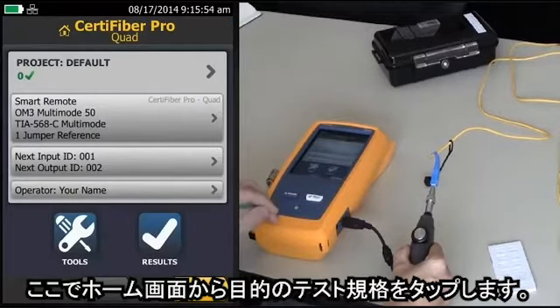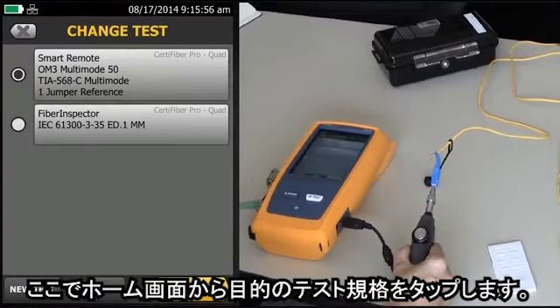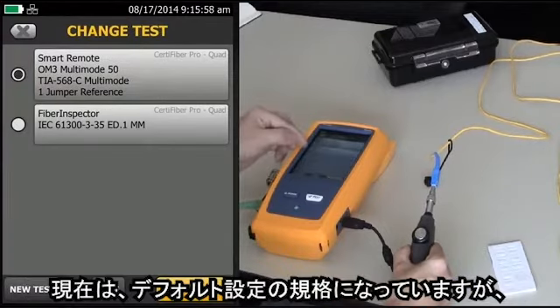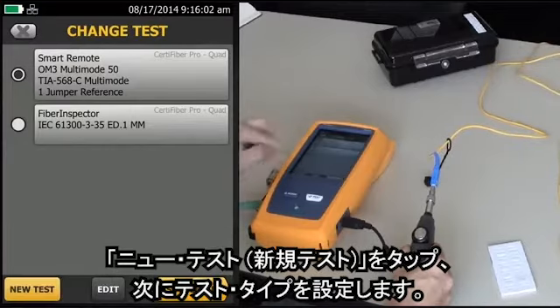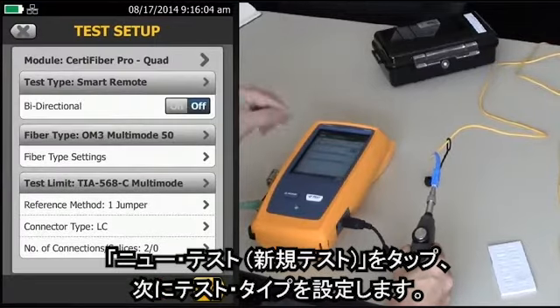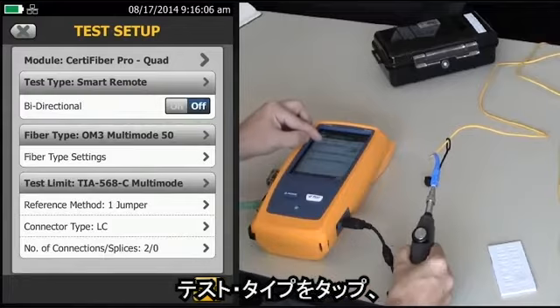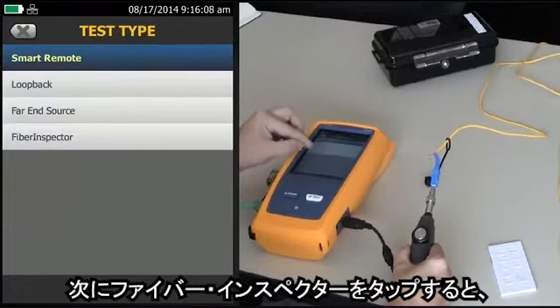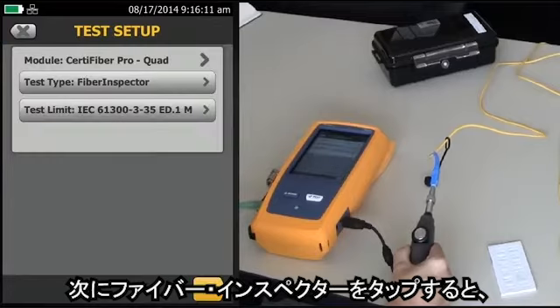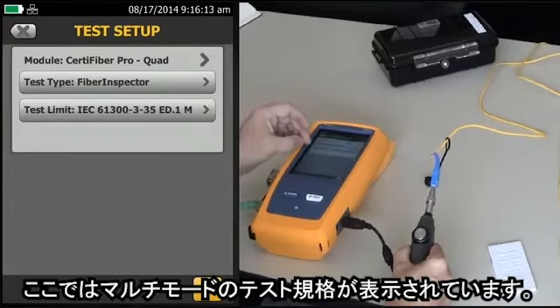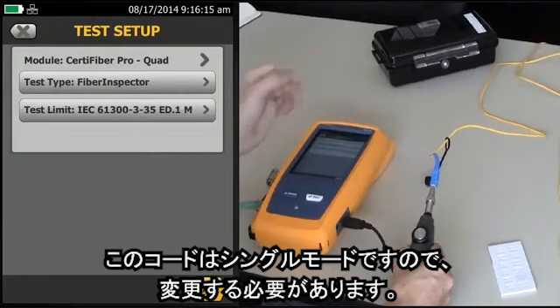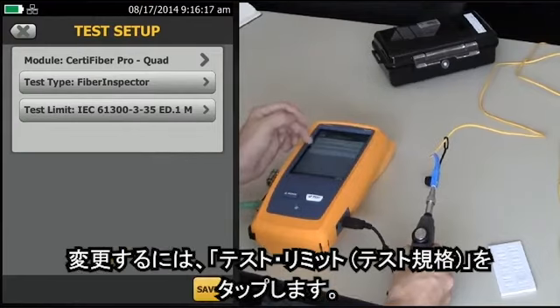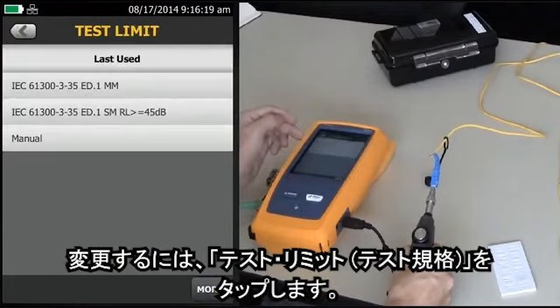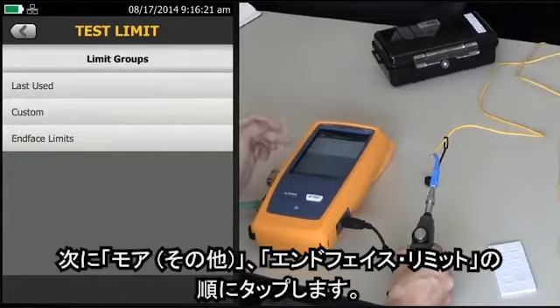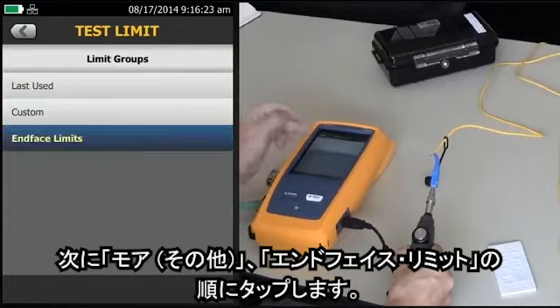So from the home screen, I'm going to tap where my test limit is. And actually, I've got one here as a default in the instrument, but if I tap New Test, we see test type. If I tap test type, Fiber Inspector, and it will give me the test limit for multi-mode. Well, this is single mode, so I need to change it. So to change it, I tap test limit, more, and end face limits.